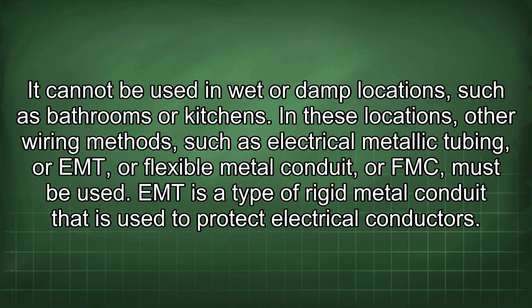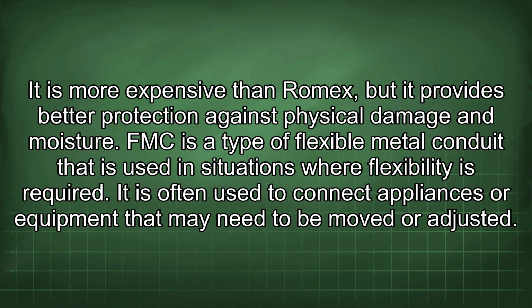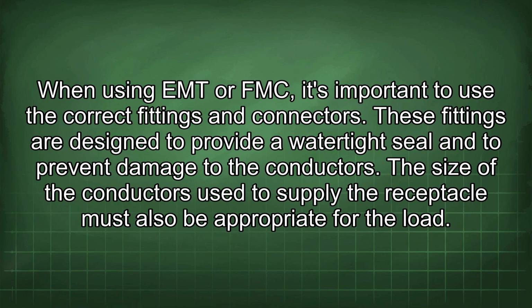In these locations, other wiring methods, such as electrical metallic tubing, or EMT, or flexible metal conduit, or FMC, must be used. EMT is a type of rigid metal conduit that is used to protect electrical conductors. It is more expensive than Romex, but it provides better protection against physical damage and moisture. FMC is a type of flexible metal conduit that is used in situations where flexibility is required. It is often used to connect appliances or equipment that may need to be moved or adjusted. When using EMT or FMC, it's important to use the correct fittings and connectors. These fittings are designed to provide a watertight seal and to prevent damage to the conductors.